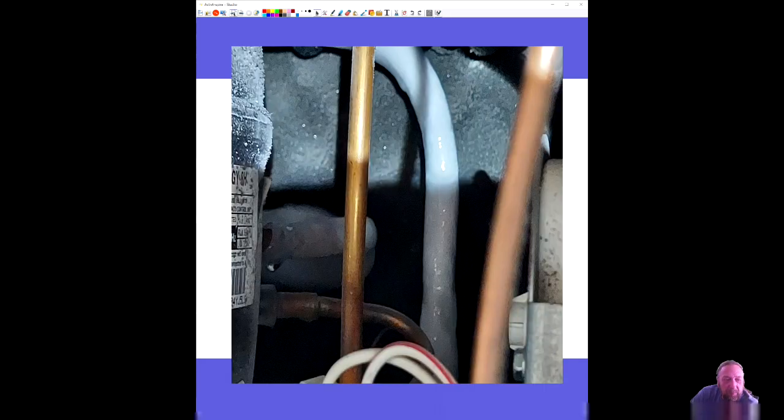So when you get there, after you've asked your customer their questions, what was cooling, where it's cooling, if they saw or heard things running, how do you begin? What's the first thing you do? Besides get the model and serial number off the unit, that's the first thing you should do. Go ahead, Jonas. You can check the temperature of the freezer or the refrigerator with the gun. Okay. Do you know that the gun only checks the temperature of the wall?